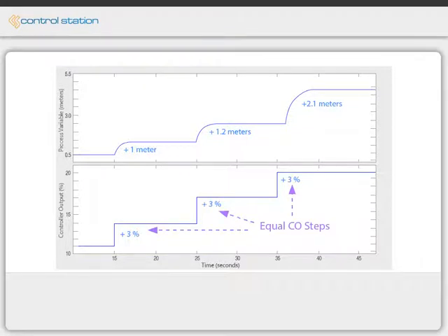However, the behavior of the process as it responds to each controller output changes. By the time the final steps are reached, the process behavior becomes quite different. Thus, the gravity drain tank's process is nonlinear, and this is evident because the response of a measured process variable changes as operating level changes.